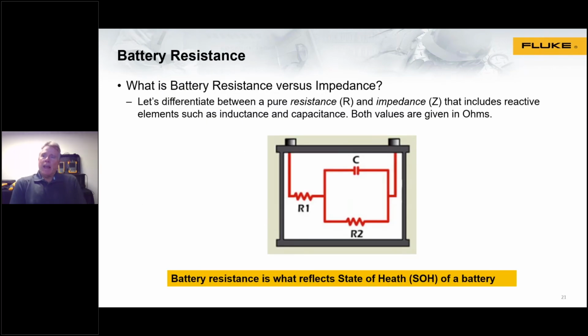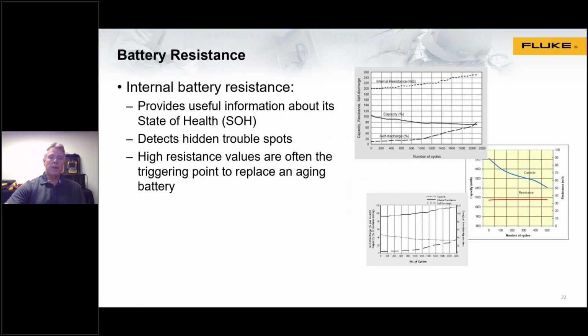So really we're going to be looking at battery resistance versus impedance. So really the number that is most indicative of the state of health of a battery is actually the resistance measurement. So that's really the gold standard for checking and determining battery health. So when you look at battery resistance, typically you'd use a tool called a battery analyzer to measure these very low internal resistances and to look for trouble spots.